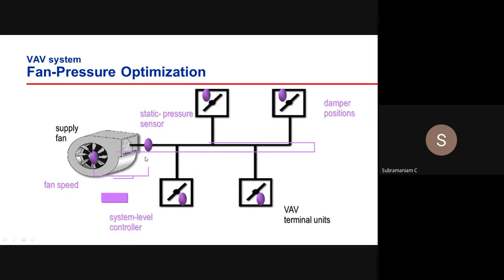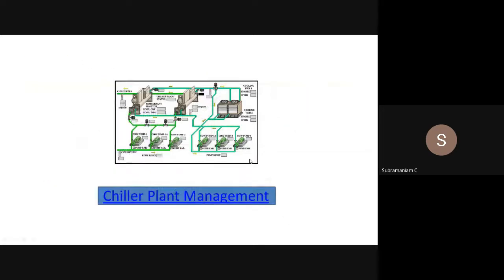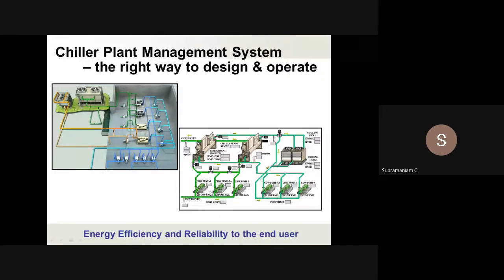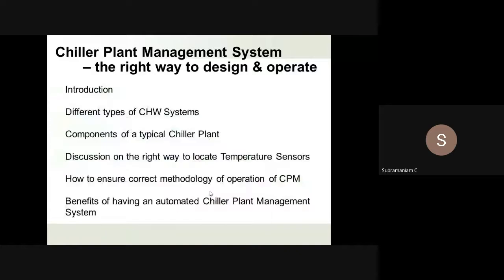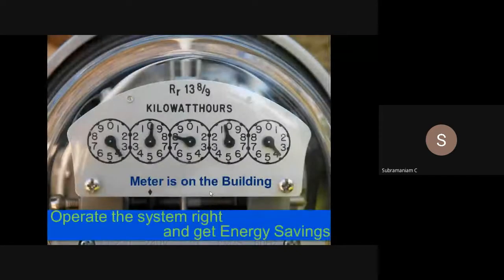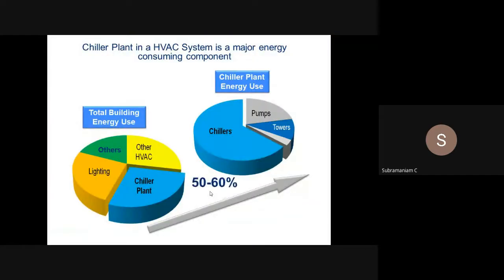And actually 90.1 talks about resetting that set point also to achieve energy saving without compromising on cooling also. So that is again there. Then chiller plant management is something which is an important thing in our BMS control. So we have the meter on the building, because as you know, the percentage of saving comes from the chiller plant. It's almost 50 to 60% in HVAC there.